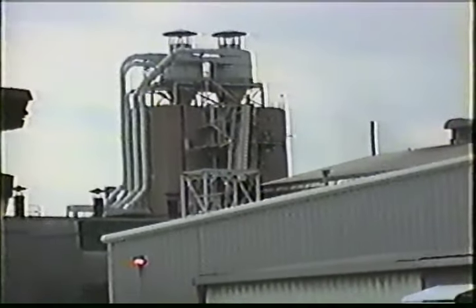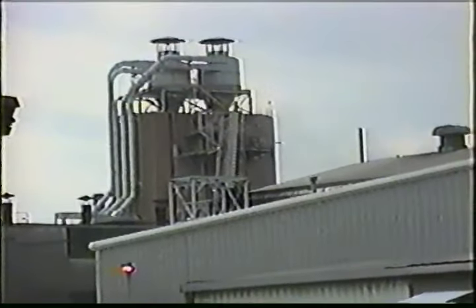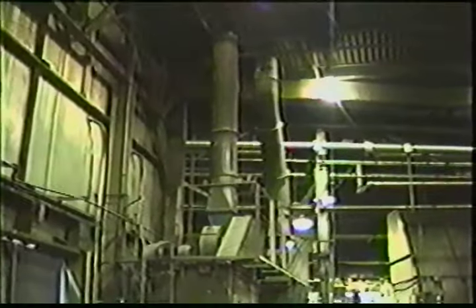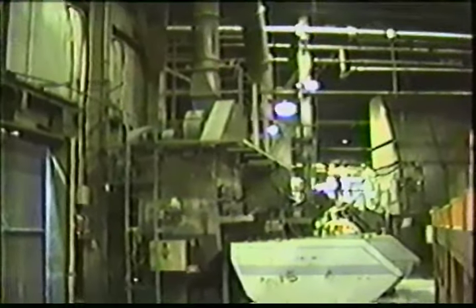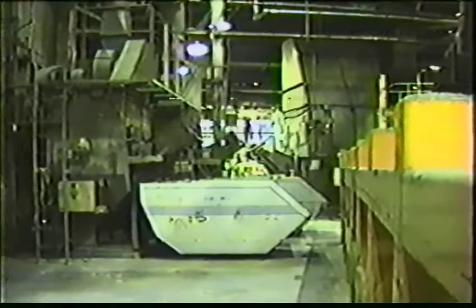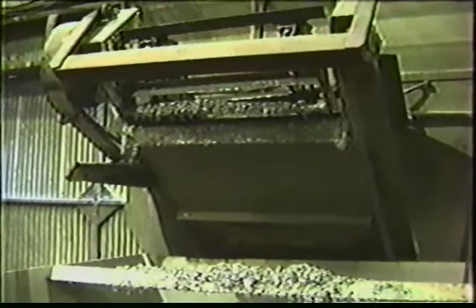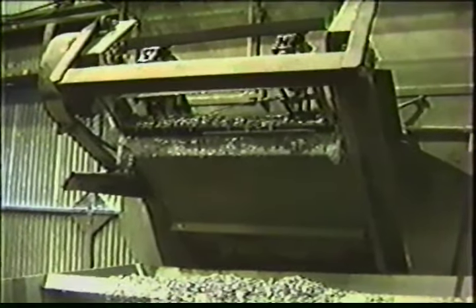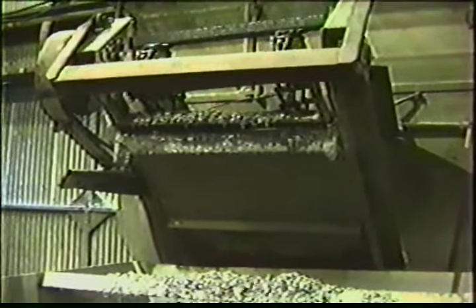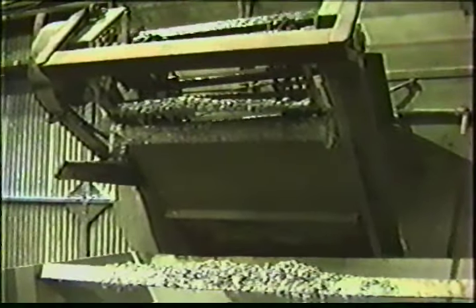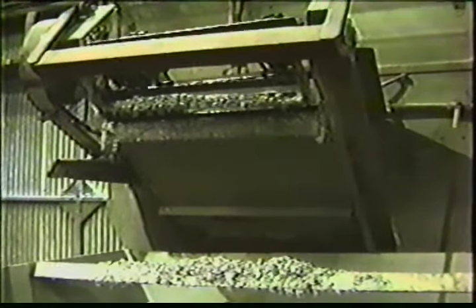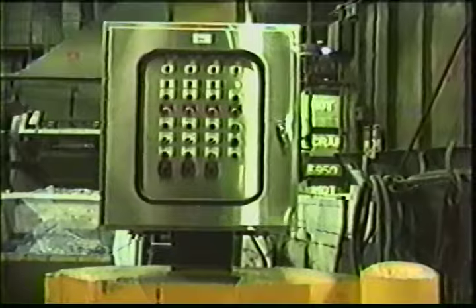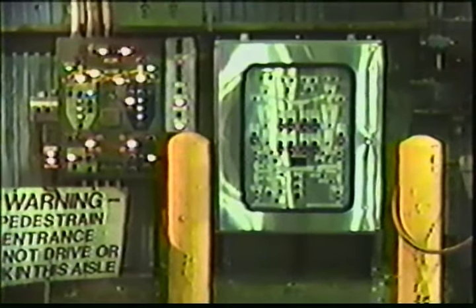The ingot plant has 4 N-type rotoclones which pull the fines from the material streams. A cyclone in each upper silo room separates the fines from the incoming scrap. The ductwork carries these fines to the number 1 and number 2 rotoclones. The fines are removed by the rotoclones after being suspended in water. Proper operation of the rotoclone is extremely important in controlling the accumulation of fines. Finally, when new offline equipment is installed or existing equipment is changed, make sure the design and operational guidelines according to the Alcoa engineering standard are followed.